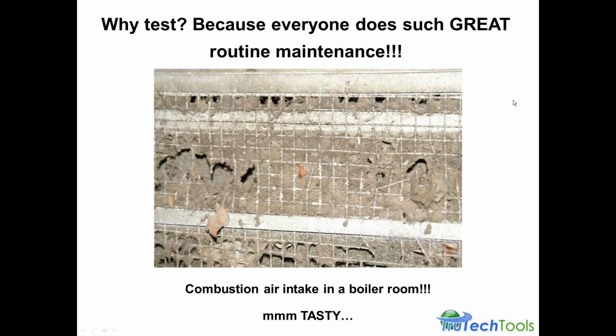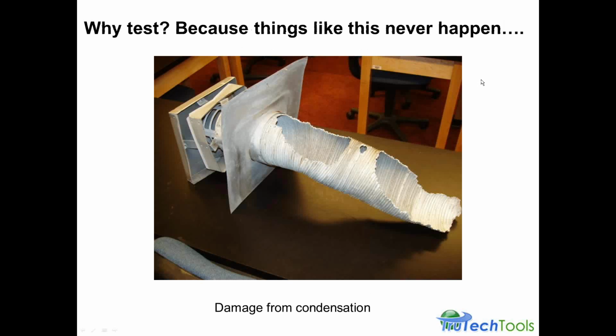We were talking earlier about situations changing and why test an appliance that's not adjustable. Well, here's a good illustration, because everybody does such a great job during routine maintenance. This is a true picture taken of a combustion air intake in a boiler room. It was really hard to believe that any air could make it into that combustion air intake. The system was designed to move air through that open grid, and that grid was so clogged there wasn't enough air moving through, and that can cause combustion to be severely compromised.